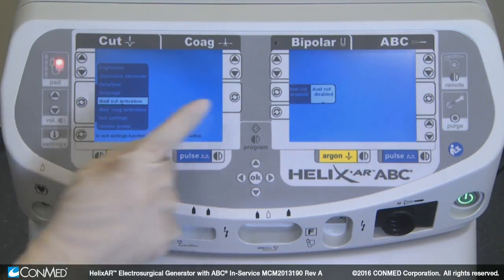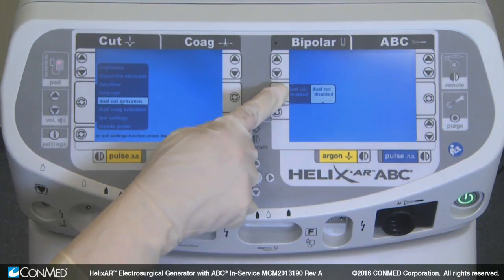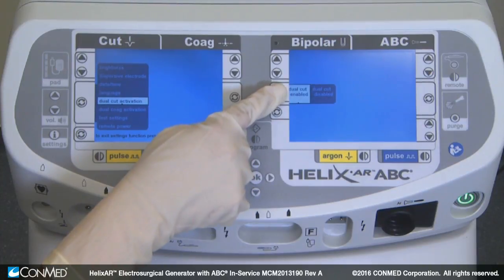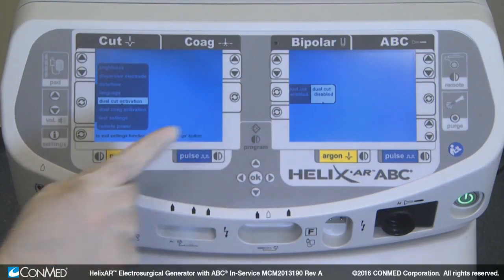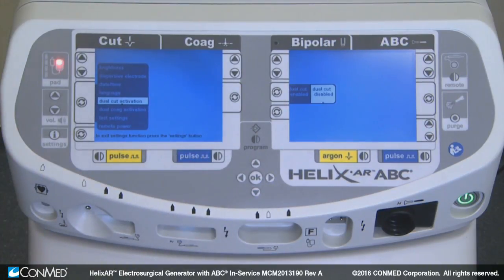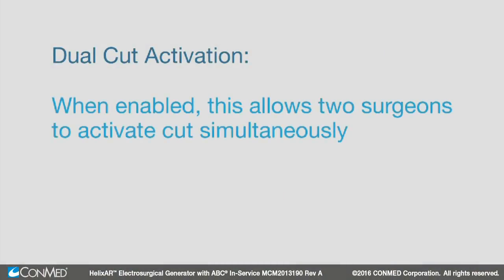Dual cut activation enables or disables dual cut activation. When enabled, this allows two surgeons to activate cut simultaneously.